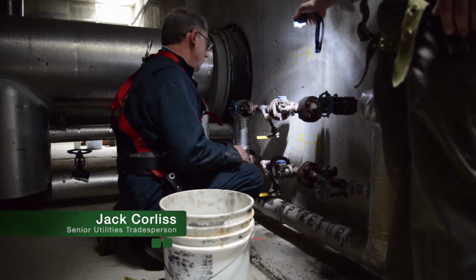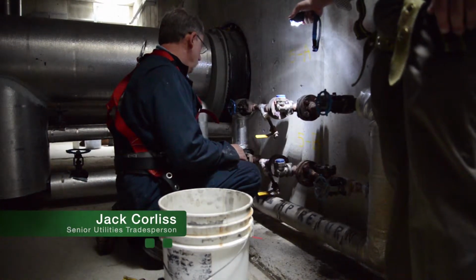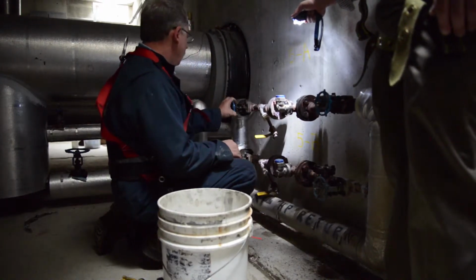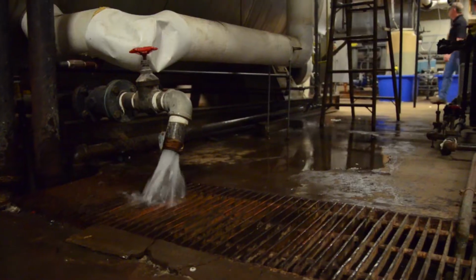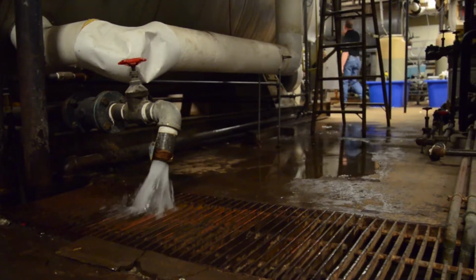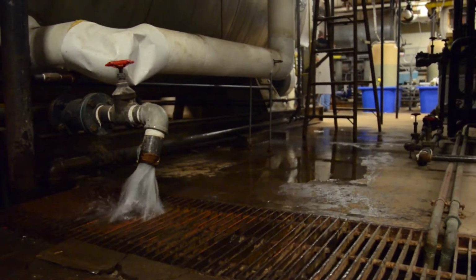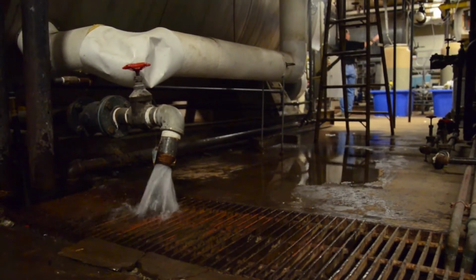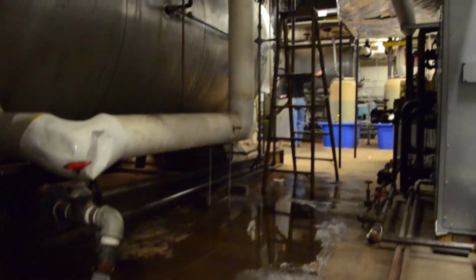They'll make sure the building is getting the appropriate amount of steam and at the right pressures. And then they'll shut everything down, and we're essentially back up again. When we start it back up, we position different people at different manholes. We open a drain on the steam side, so if there's any water ahead of the steam, it comes out. And then when the steam gets to that point, they shut it and let the traps take over.